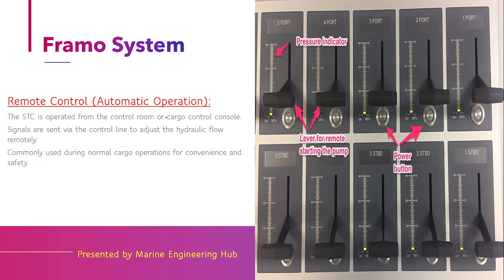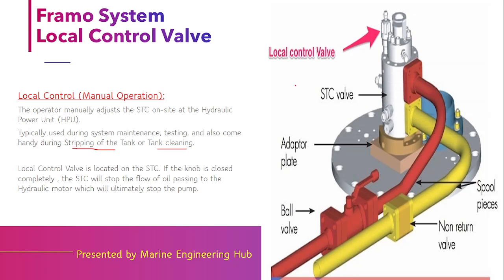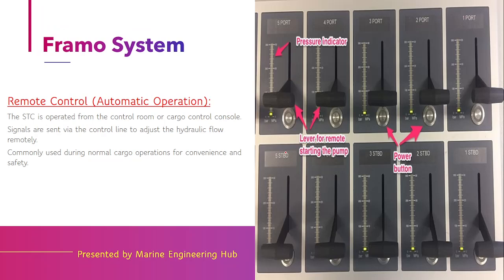Now for remote operation: a panel is provided in the CCR — the Cargo Control Room. When you want to operate the Framo pump remotely, click the button and push the knob in the required direction. The pressure will start to build up gradually. The gauge shows 100 bar, 200 bar, and 300 bar. Depending on the requirement — say 150 bar — you put the knob at that position. Different pumps have different port knobs: 5-port, 4-port, 3-port, etc., giving the convenience of remote operation.